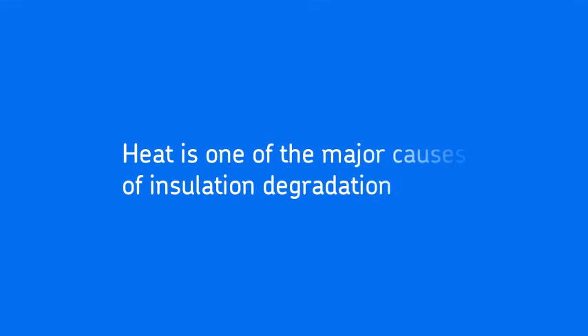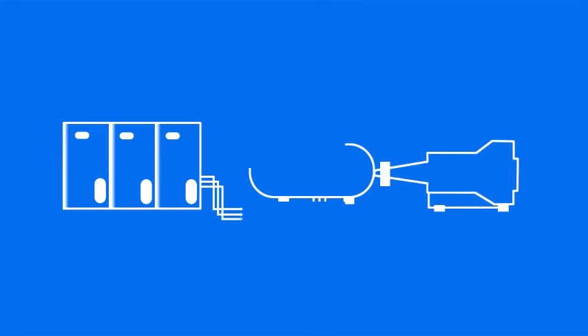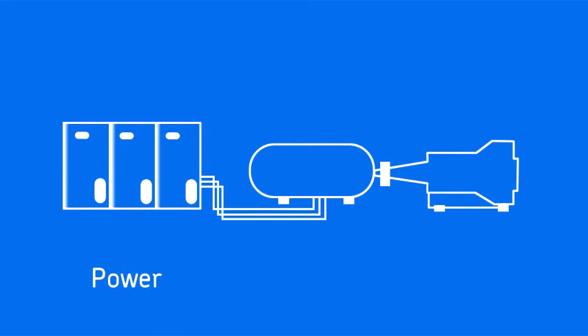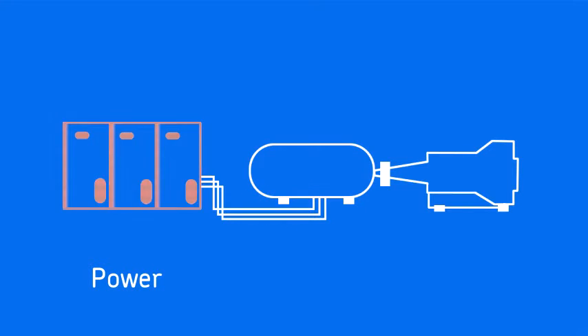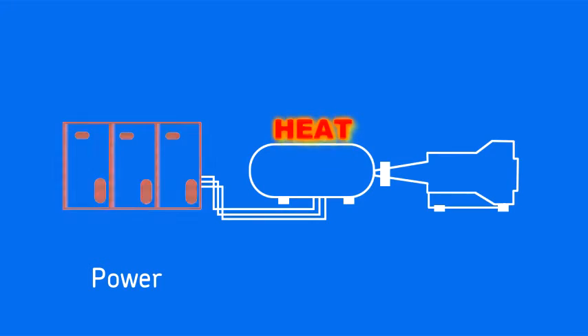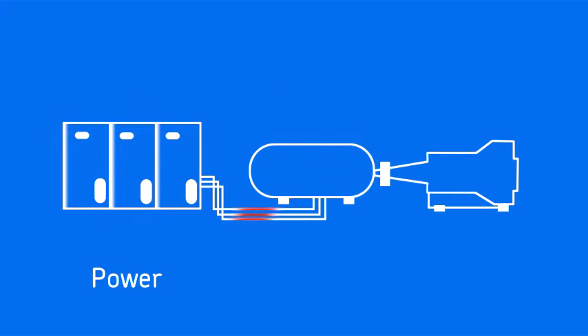One of the major causes of insulation degradation is heat. To understand more about what causes excess heat in the motor, let's look at the entire power motor load system. Electric machines are designed for good incoming power conditions. When power conditions deteriorate, excessive currents can flow in the machine, generating excess heat and shortening machine life.